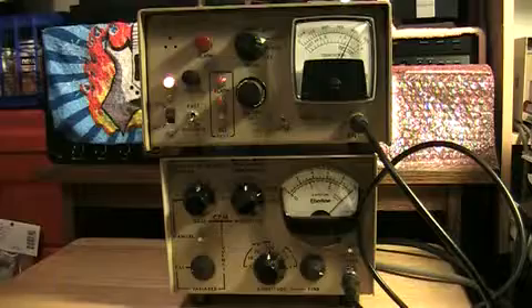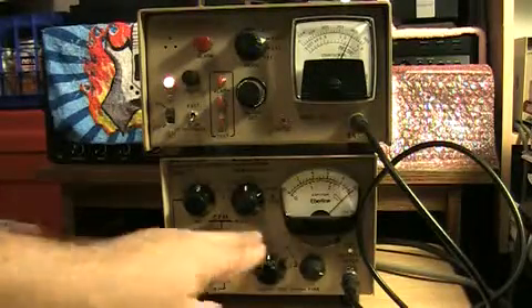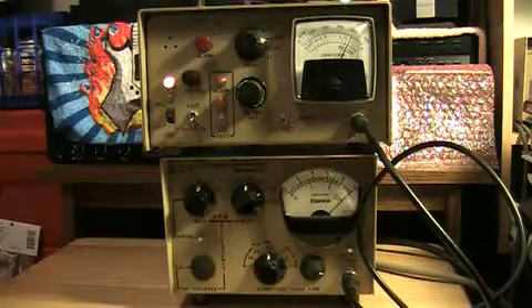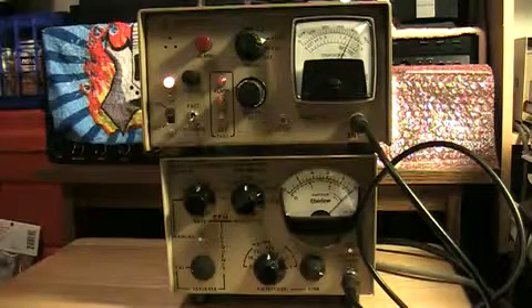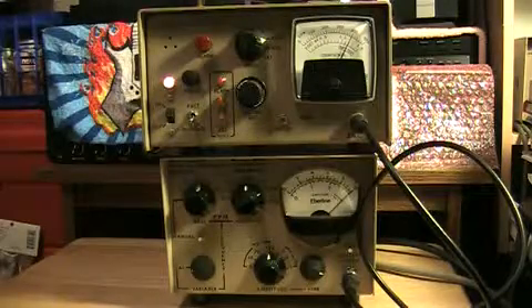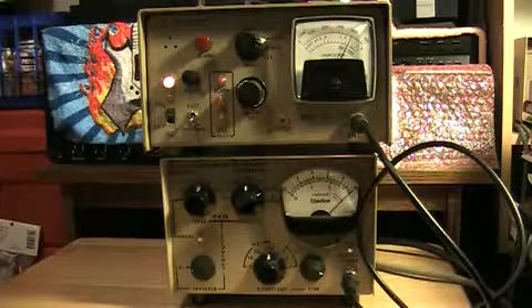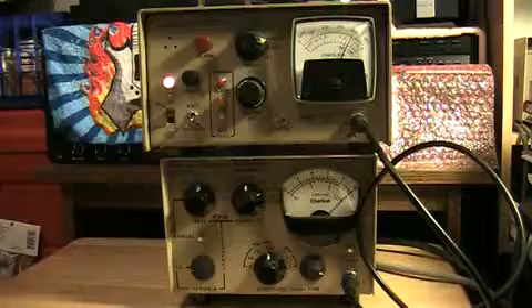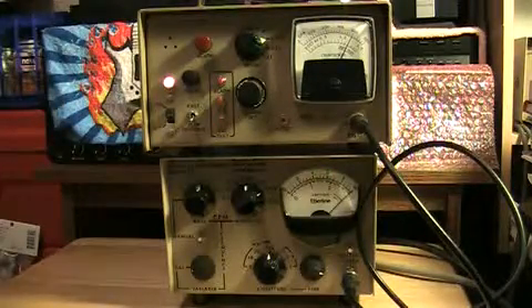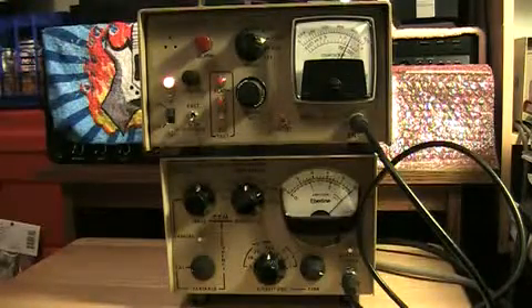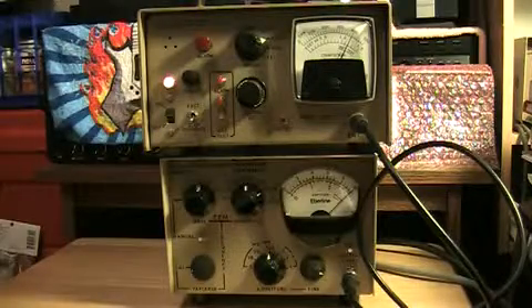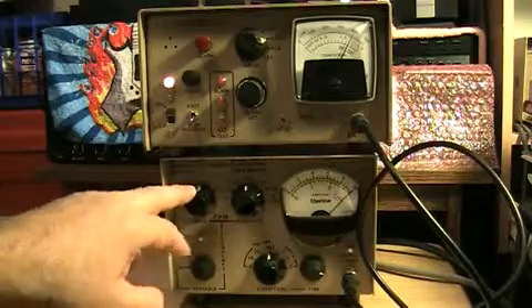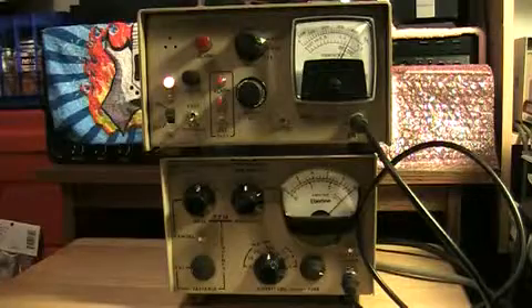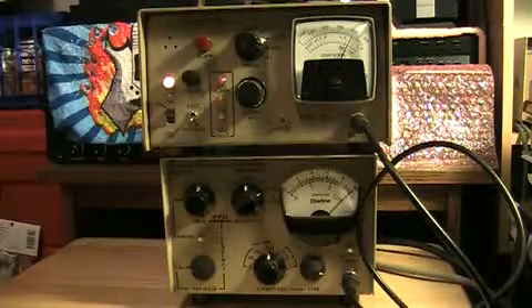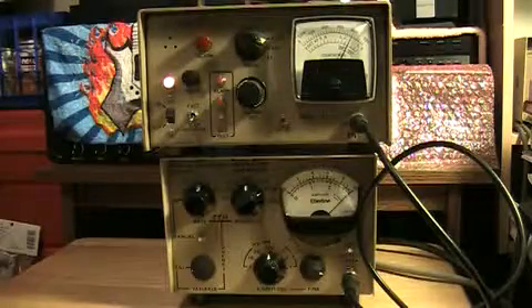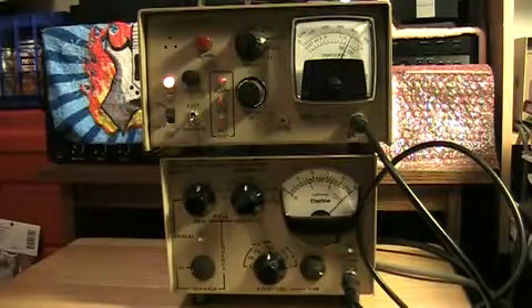Like I said, when I got this originally, hooked it up to an oscilloscope to check these voltages and the pulse rates. It's right on the money. So you don't have to do this too often. The last few times I've done it 3 times so far, a couple times a year. But I did it about a couple of weeks ago, first part of January 2010. Really nothing needed to be adjusted. I chose the Ludlum just for sake of convenience. It's got the adjustments in the back. The other Eberline, so you have to take off the cover to get access to the adjustment screws. But you can see it's right on scale, times 4 here, 400 up here. Not really a necessary item, but in my case, it's nice to have. That's the calibration of Geiger counter with the Eberline MP2 mini pulsar.